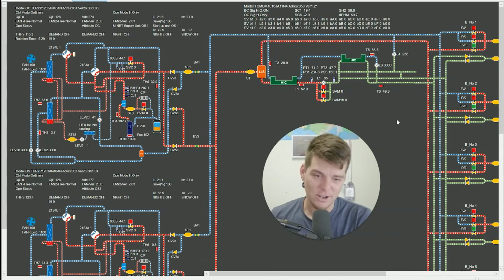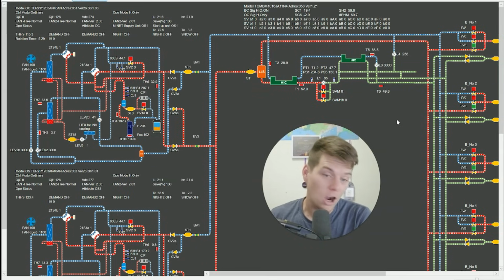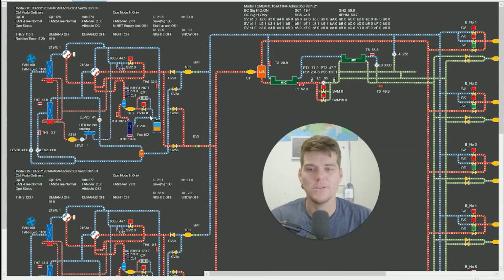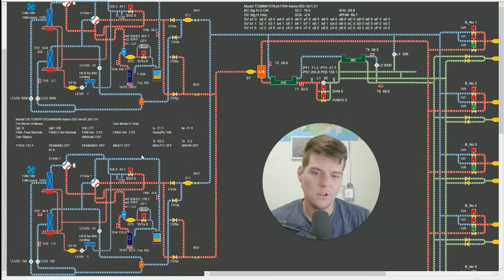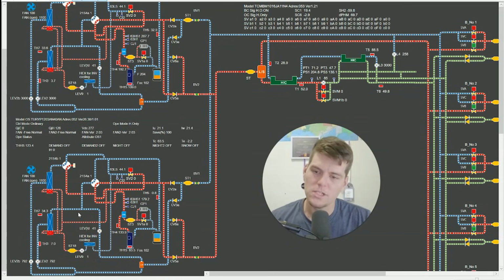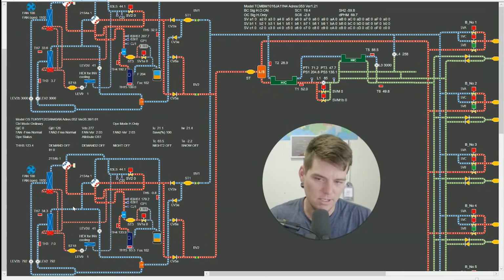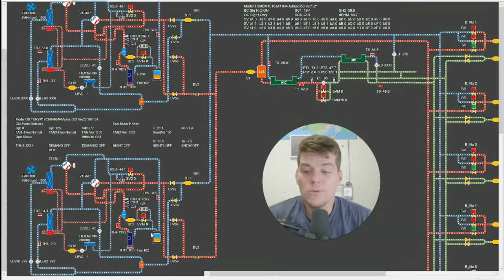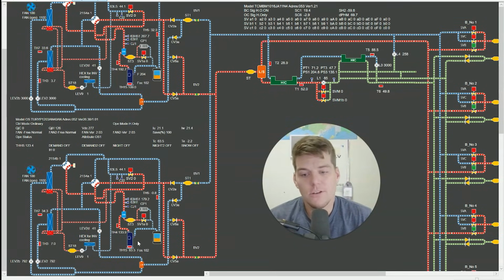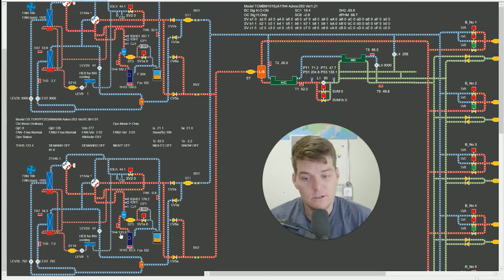We know high suction superheat, high discharge superheat in the master module. We know we have low subcooling across all indoor units at low valve pulse, and the submodule is flooding. So let's go to the submodule and show it some love. Why are you flooding, submodule? Wish we could ask, but we wouldn't get an answer. But there are things here that are red flags. The red flag is the discharge superheat is low.